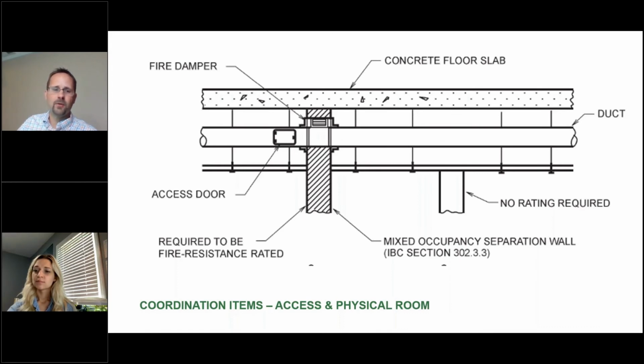And then it needs to be coordinated in the field that you don't have anything else running underneath those. Even if on your mechanical drawings you have these located in the access doors in the most accessible location, and then conduit gets run underneath them and they're not accessible, that's going to be a problem for the project. It could be a 50-year life for that damper, and someone has to go up there and try to access that. So it's important to be really protective of these access spots.